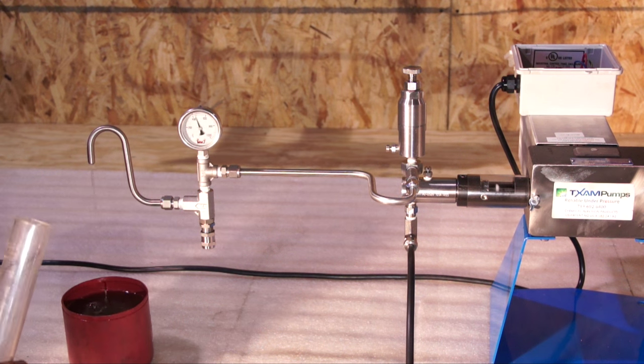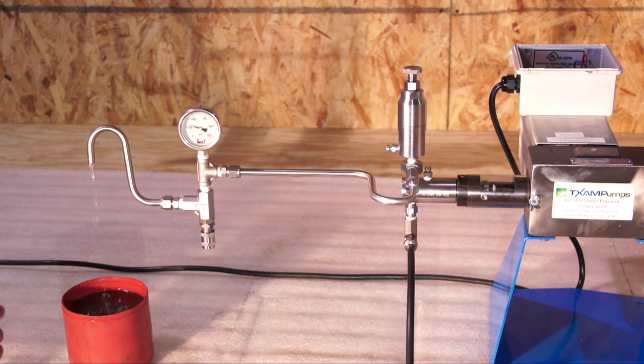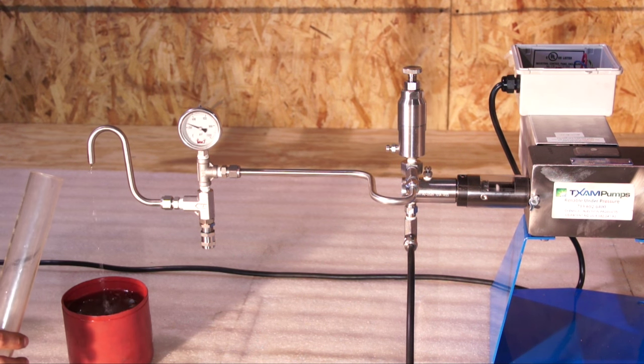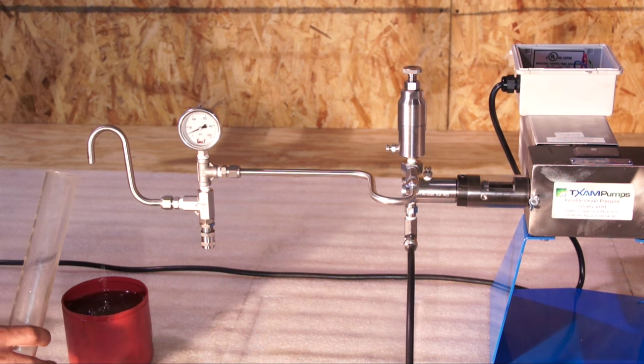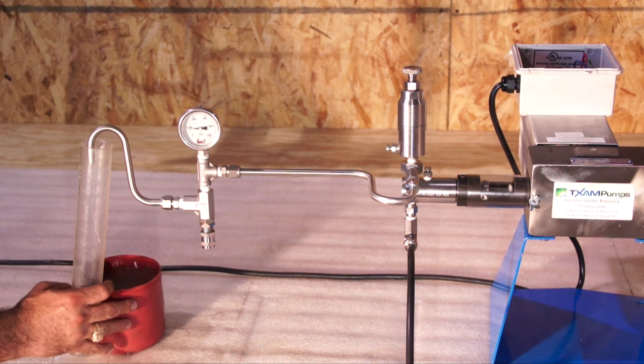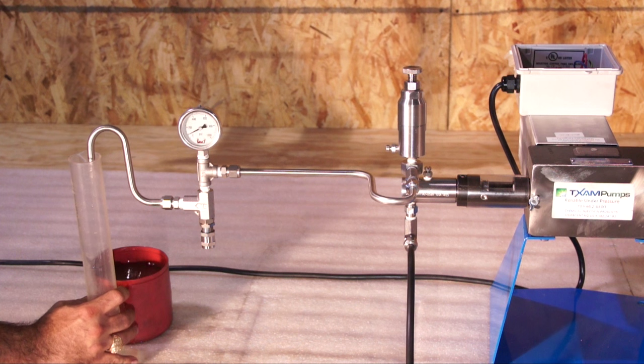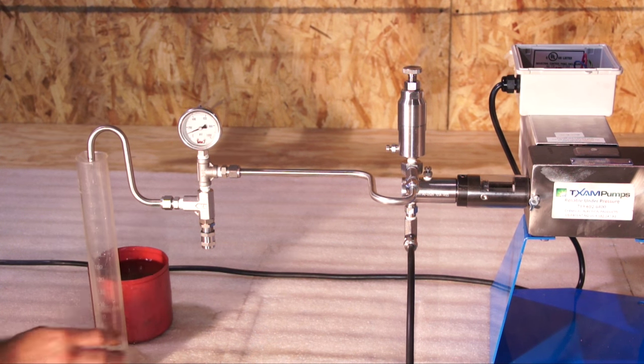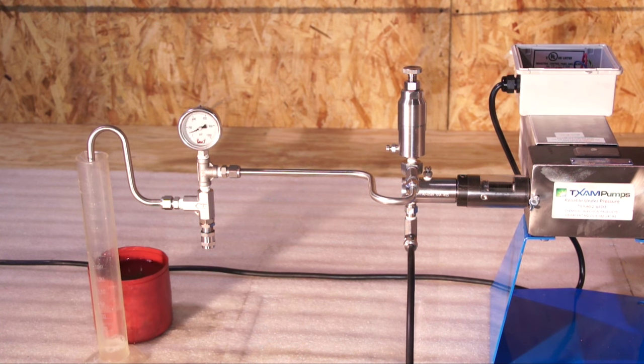450 psi discharge. The pump is stroking at its full capabilities, max controller setting. You'll see when that pump strokes, you have a steady flow of chemical.